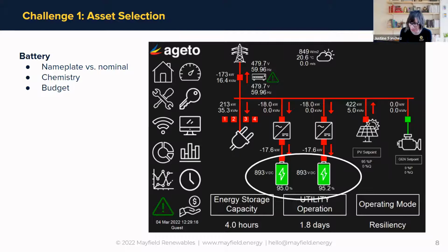One thing to add from the project we worked on together is how we chose our batteries. There were a couple factors I didn't realize until we were in the middle of it. One was that not all energy storage systems can utilize the full capacity of your array. We had an existing 255 kW array, and one battery option would have required us to segment about 100 kW of that PV off the energy storage system - it couldn't absorb that much through the battery. I'm not exactly sure what the limiting factor was, but that was one consideration.